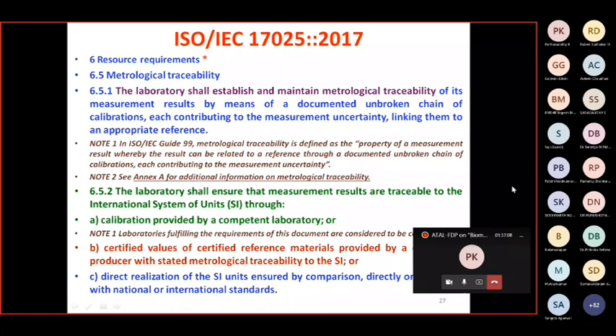So when you do the calibration at a NABL laboratory, nobody will ask you about traceability, because when they give certification to that laboratory, they ensure all their standards, calibration blocks, and reference standards are provided with an unbroken linkage to international standards. In case you are doing calibration with other than NABL accredited laboratories, it is your responsibility to ensure the reference standard used by your external service provider has a linkage to international standard.